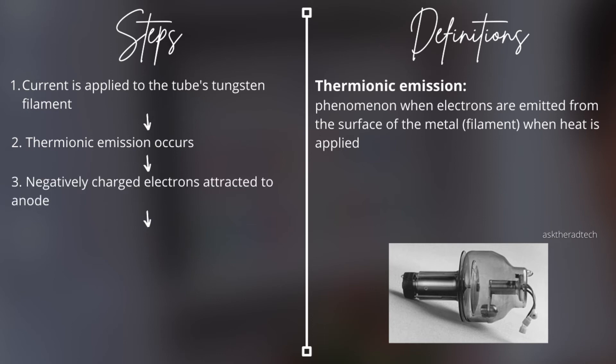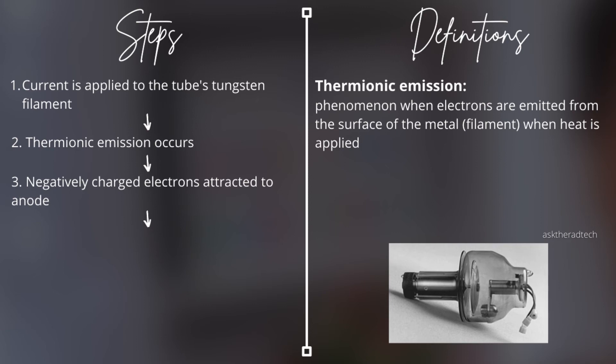Step three: due to attraction, the negatively charged electrons that are produced are drawn across the tube toward the positive terminal — the anode. The electrons hit the tungsten target of the anode with very high energy and velocity, where they dramatically stop. The energy with which they hit the target is determined by the tube's selected potential voltage.